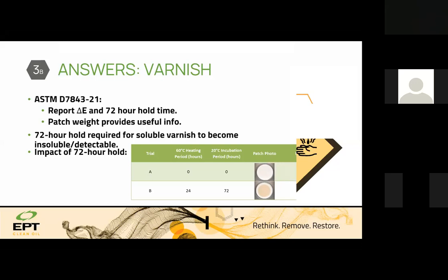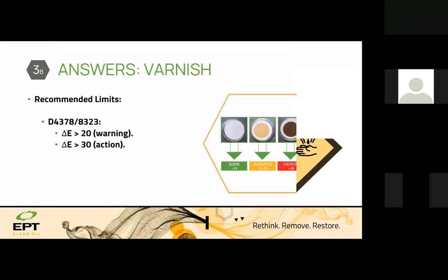oil. If we don't do that test rightly, in the right professional way as per ASTM standard, you will get low MPC values. I have seen some filtration companies which remove only insolubles, using depth filtration and so on. They are doing the test on site without following the ASTM standard and showing a very white patch, no varnish and so on. This is not the right way. Let us do it as per ASTM.